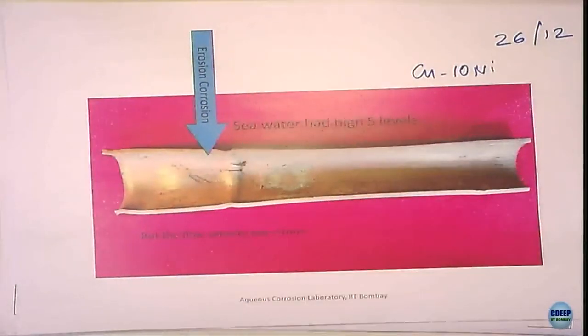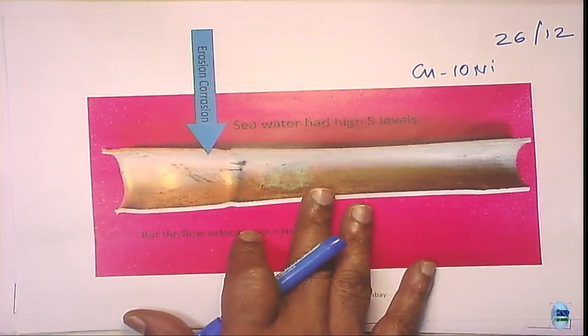The velocity is so low, look here, the velocity is 1 meter per second, then still why does it happen? We looked at the water and it had a small amount of sand particles. So the critical velocity that you see from the textbook, which allows you about 2 meters per second, is no more valid here.